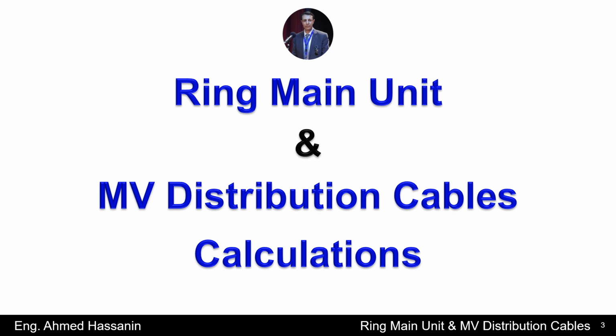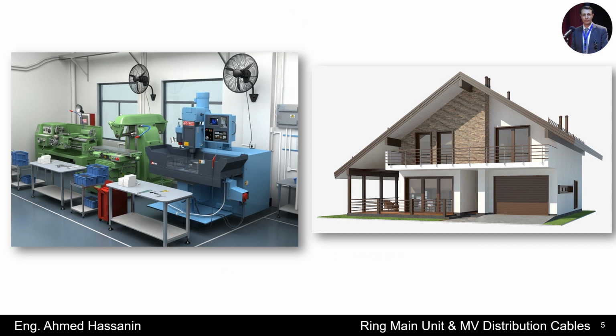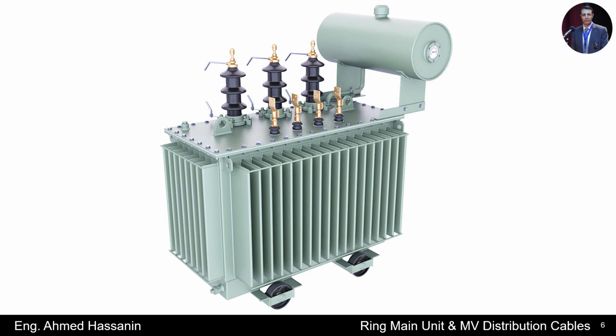In this course, I will talk in detail about the introduction. In this introduction, I will talk about the last part of the distribution system, which is related to feeding low voltage loads, whether domestic loads or single phase loads, and industrial loads or workshop and three phase loads, and how the electrical power system supplies the different loads with single phase and three phase voltage. In addition, we will know that the connection part between the low voltage loads and the medium voltage distribution network is a distribution transformer. And through the distribution transformer, we can obtain low voltages, whether single phase or three phase.